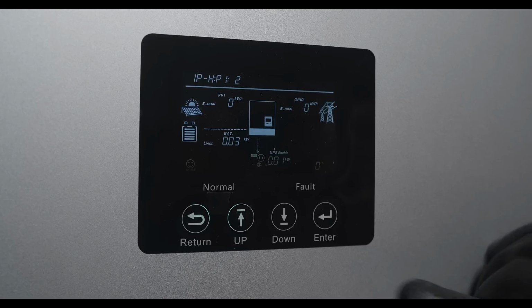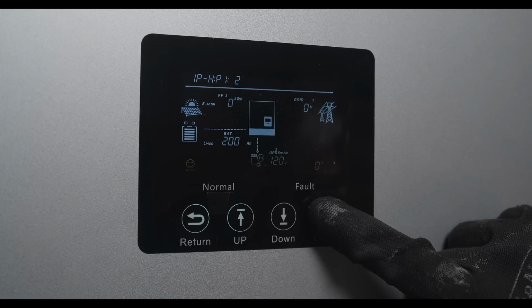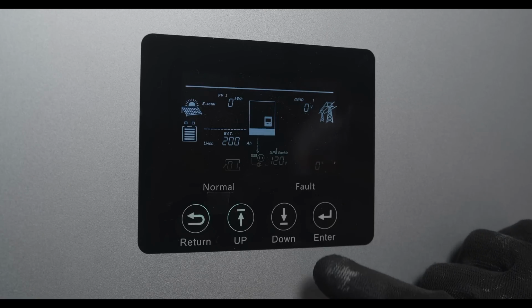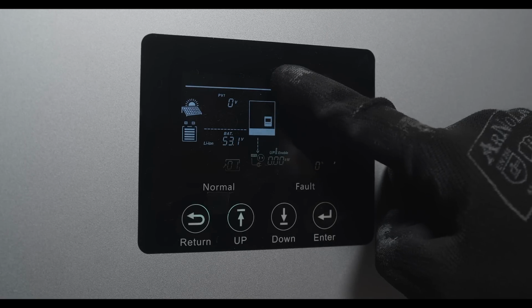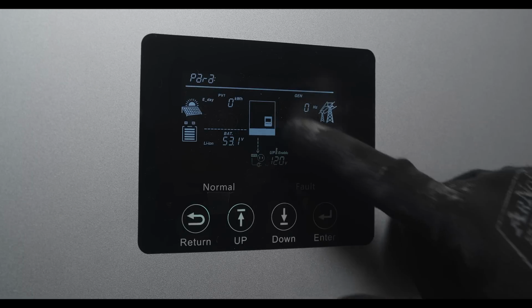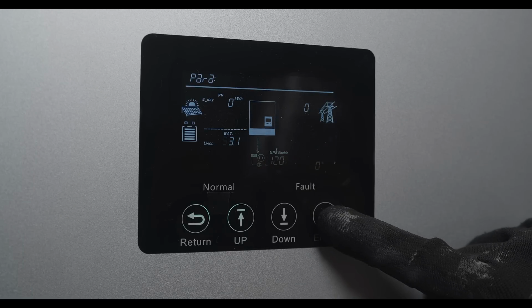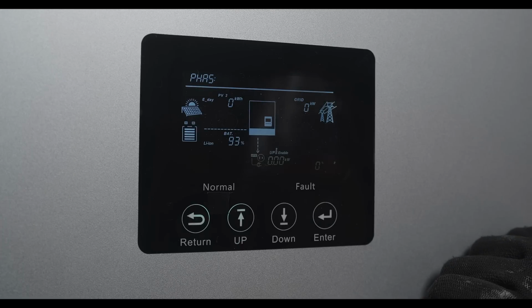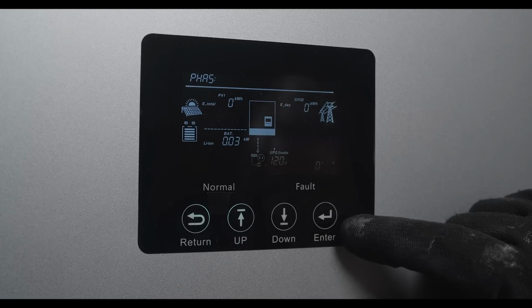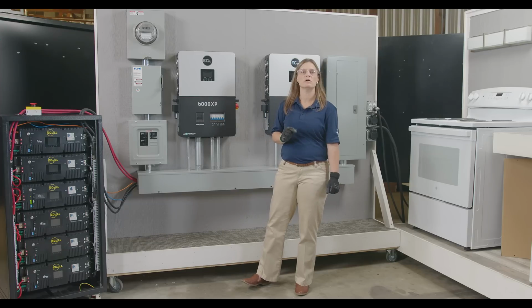Let's set this up. Hold Enter down for about 5 seconds. Top left words will start blinking. Navigate to setting 21. For split phase parallel, set it to 1pH. Parallel phase. Your LCD will show a new setting. Set the inverter to P1 for phase 1 and repeat for all inverters.